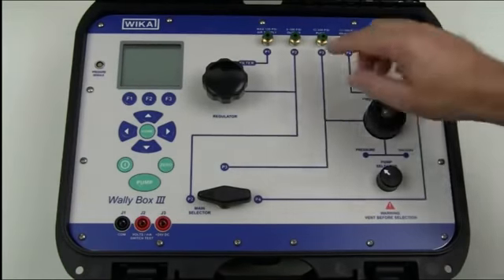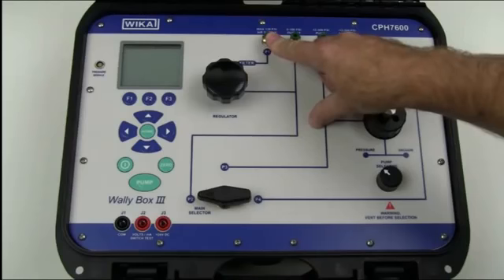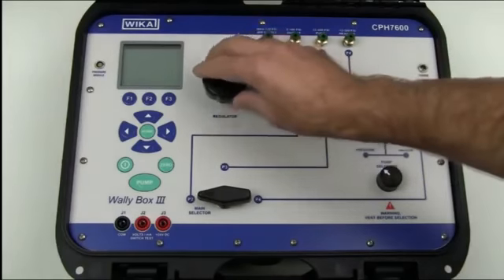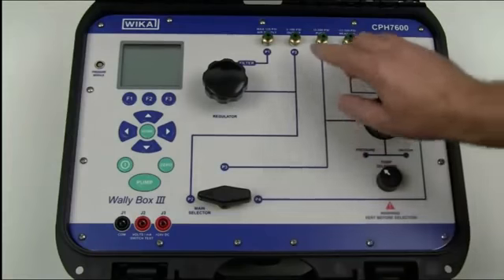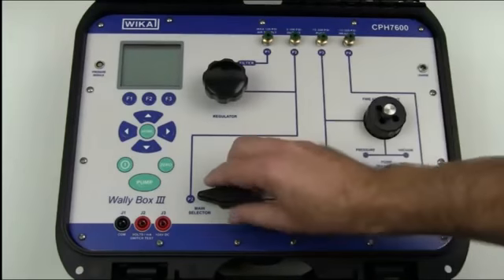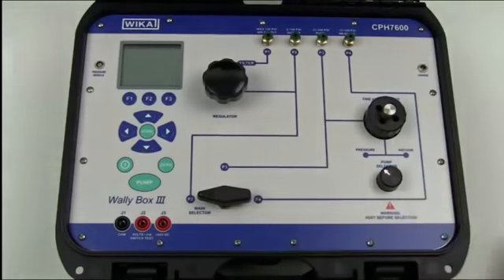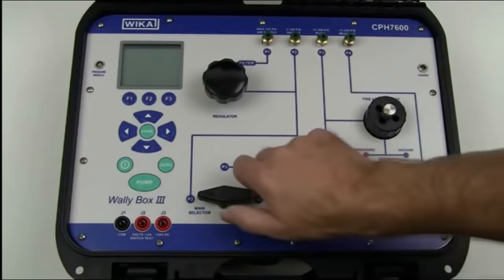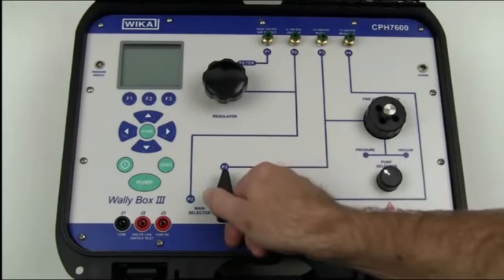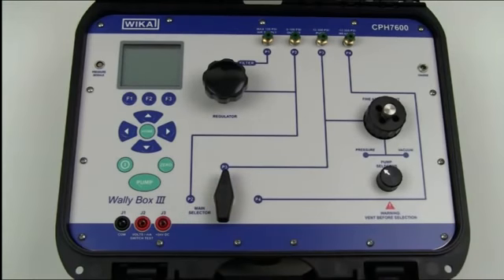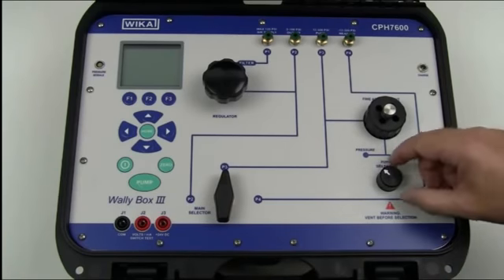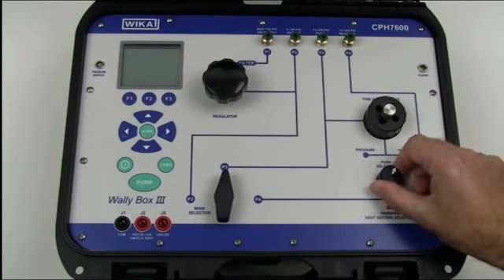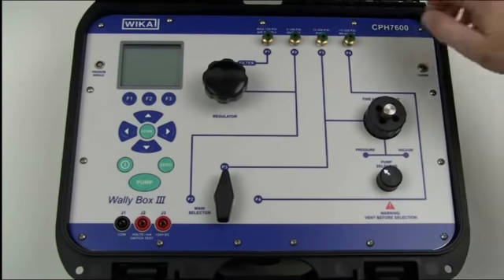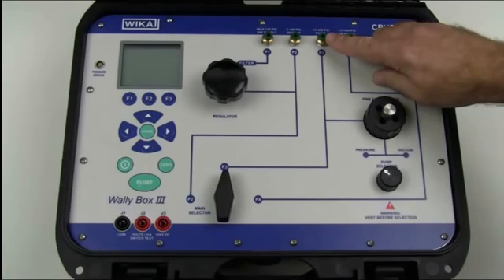The first pneumatic system, you are able to put 120 psi, and via a filter through a regulator you are able to adjust an output of 0 to 100 psi when the main selector is in position P2. The second pneumatic system is by placing the main selector onto position P3. You are then able to use the internal electric pump and then choose between either a vacuum or a positive pressure, giving an output of -12 to 300 psi.